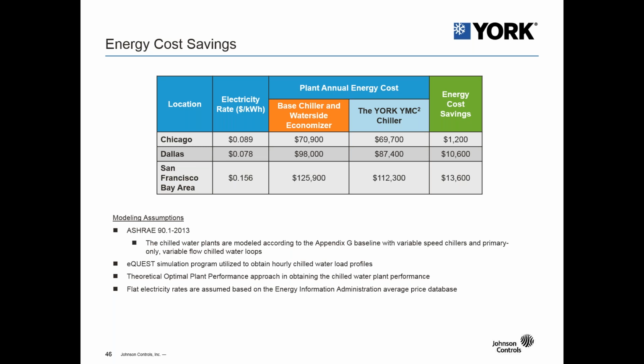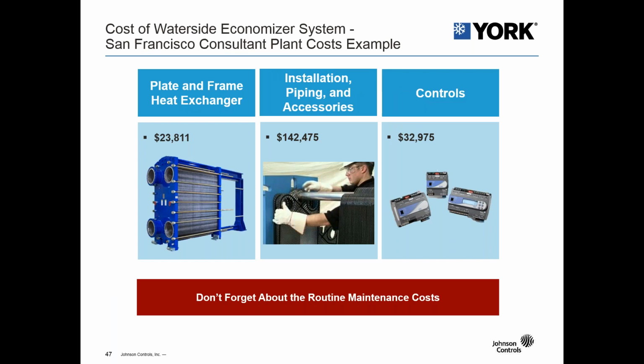So looking at the total plant annual energy cost by utilizing very low entering condenser water temperatures, we were seeing significant savings when utilizing the York YMC squared chiller. So anywhere from just over $1,000 to almost $14,000. So that's a look at just the operational costs. So the York YMC squared was providing energy savings.